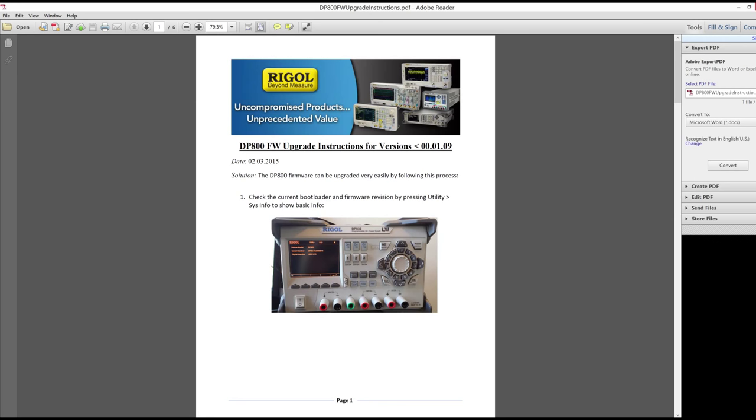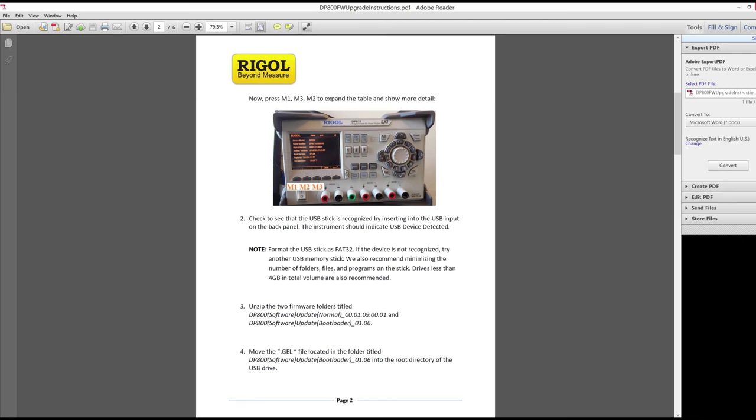First, they have you turn on the unit, hit Utility, hit Sys Info, and then on the screen the soft buttons have little secret key presses. You push them in a certain order and it does things. What they have you do is push M1, then M3, then M2 — you don't hold them, just push one then the next then the next. As soon as you plug the drive into the back, a message pops up saying 'USB device recognized.' As long as you see that, you should be good to go. I already formatted the drive as FAT32; they recommend 4GB or smaller, but unfortunately 8GB is the smallest I had.